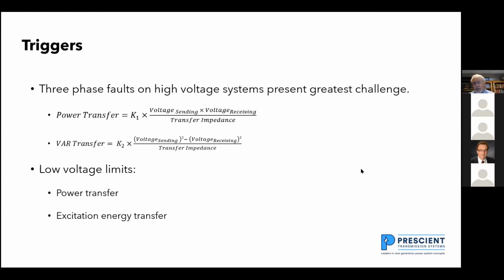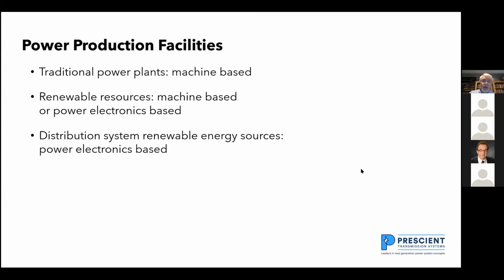And on the electrical system, we have to provide two things. One is real power, which is kilowatts. And the second is excitation energy, which is the VARs we're putting on the system. Both of these are impacted when we hit a low voltage limit. It impacts power transfer, it impacts excitation energy transfer.